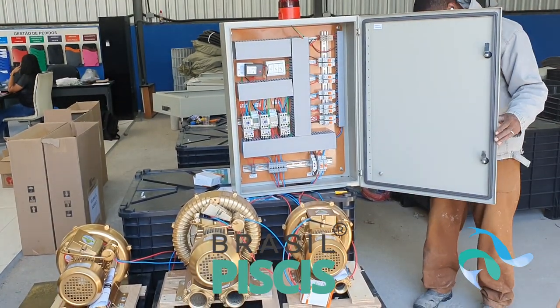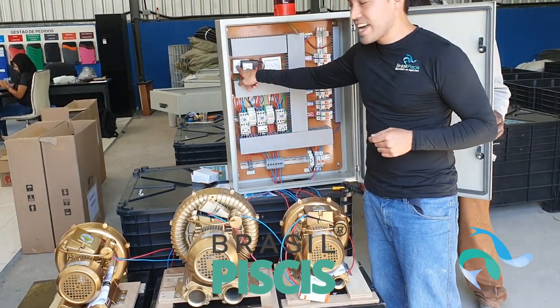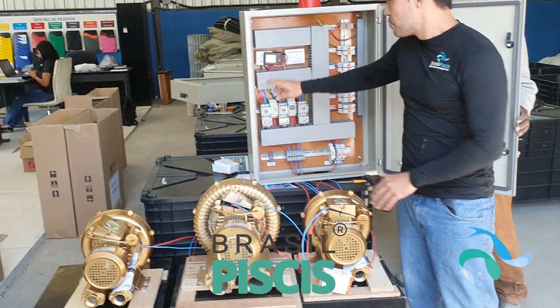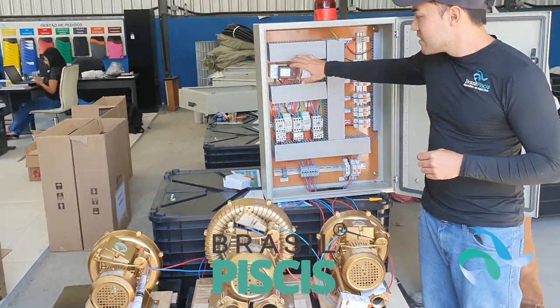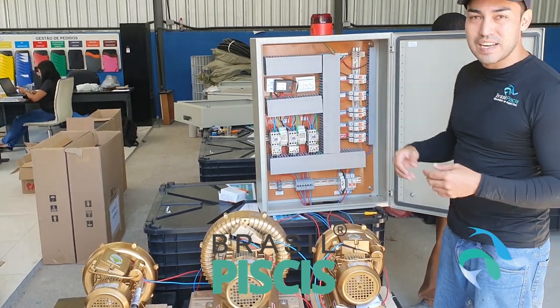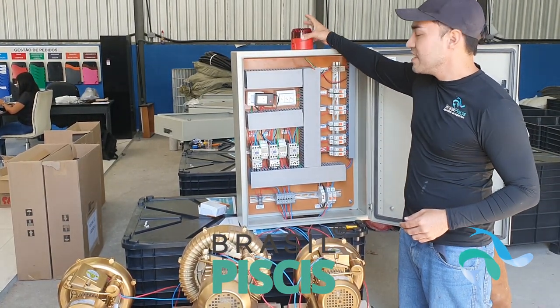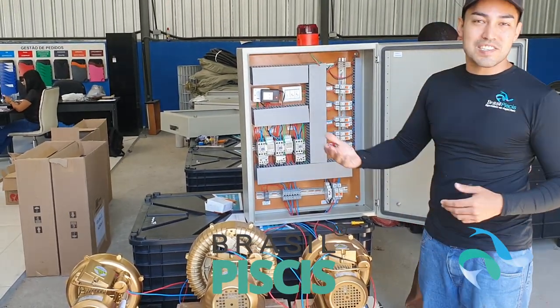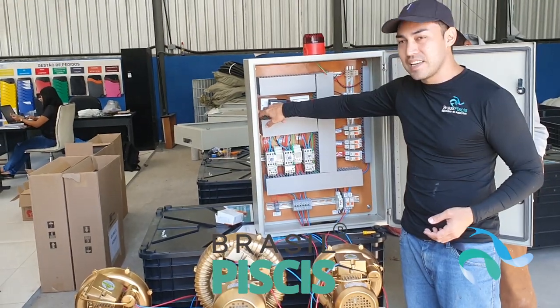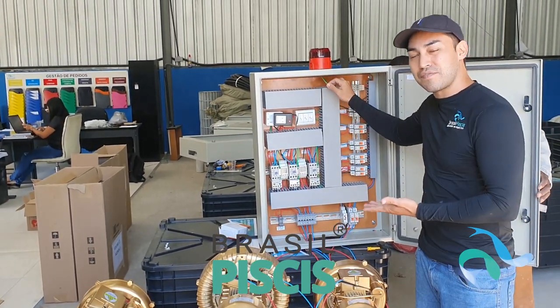Um detalhe: vocês viram que desarmou e não tocou a sirene. Por que não tocou? Eu mesmo esqueci de vir aqui e religar ela. Vocês têm que religar a sirene depois que resolverem o problema do motor. Por que a gente não deixa essa sirene sem o botão de ligar e desligar? Porque se eu não coloco esse botão, o seu funcionário vai ficar irritado e vai cortar o fio ou desplugar da sirene — e depois nunca mais vai tocar a sirene. Então é melhor deixar o ligar e desligar aqui para ele fazer isso.